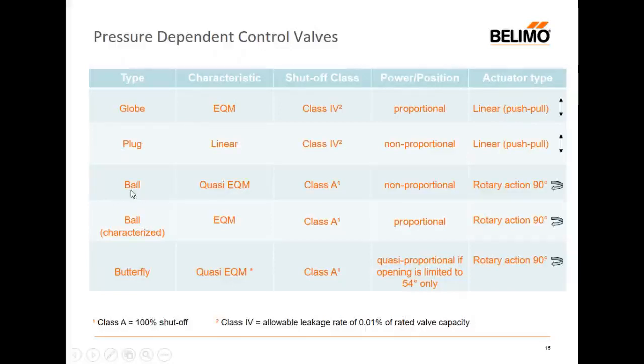Then we look at a ball valve. A regular ball valve is quasi-EQM. We saw it earlier. Not really suitable for proportional control because it's not stable. It has got class A shutoff, but it's a rotary action. And so there's some benefits with rotary action. We're not pushing against the pump. We're rotating against the resistance of the seals holding the valve in place. And of course, rotary valves, if you're a ball rotary valve, tend to be less troublesome in dirty water because they wipe themselves clean as they rotate.